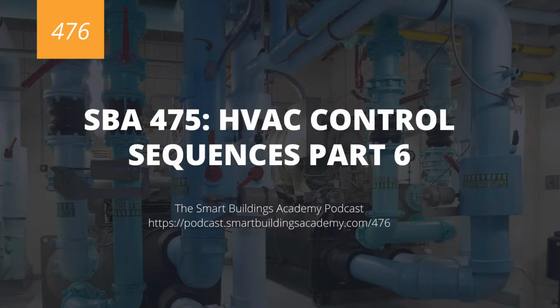So from here, we're going to move on to our air-cooled chiller sequence of operations, and then I think we'll be done with this episode. All right, so in this sequence of operations, our air-cooled liquid chiller and chilled water pump make up this chilled water system. Now, it's in operation year-round in this sequence because maybe they're handling some process loads in an IDF or an MDF, and they just want to have that chilled water. And this chiller, the pump, is running constantly.